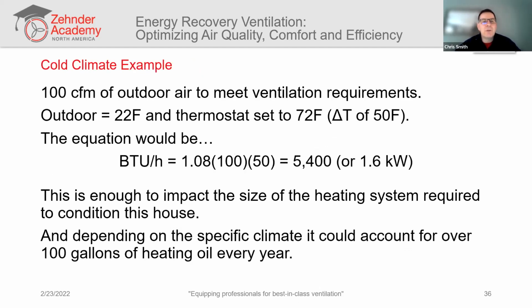So let's say we're ventilating with an exhaust fan only, just as an example, of 100 CFM. That's our rate: 100 cubic feet per minute of outdoor air is being sucked into the house through infiltration. It's unconditioned. Let's just say the outdoor air is 22 degrees. It's a brisk winter day. And the indoor set point is a common 72 degrees, a comfortable temperature. So our equation would be 1.08 times 100 CFM times 50 degrees Fahrenheit, and we'd get an answer of 5,400 BTUs per hour. So 5,400 BTUs per hour, or 1.6 kilowatts, would be the energy being wasted, or the energy penalty associated with using a bathroom fan to achieve a 100 CFM ventilation rate.